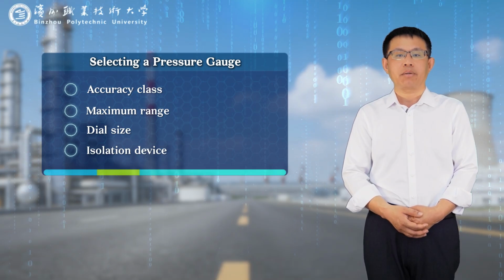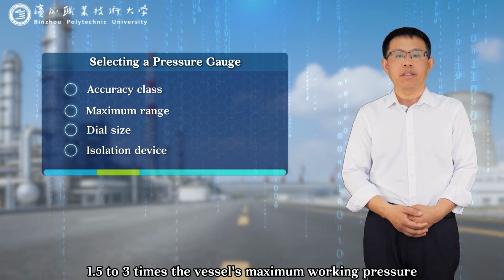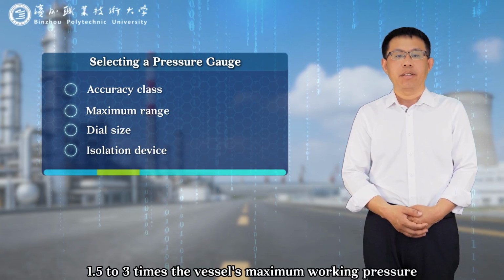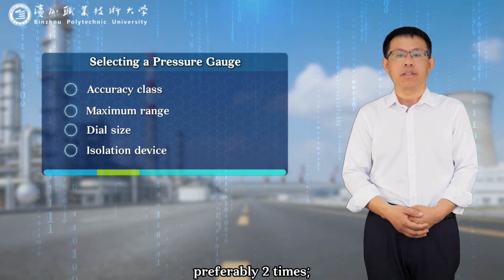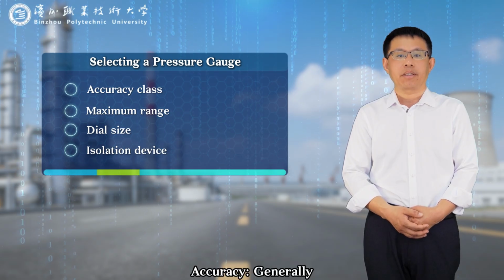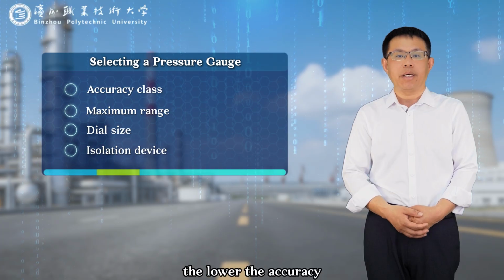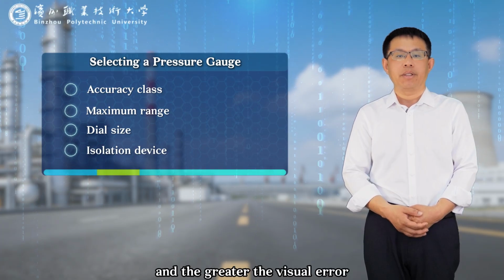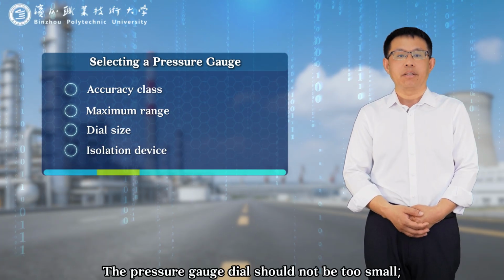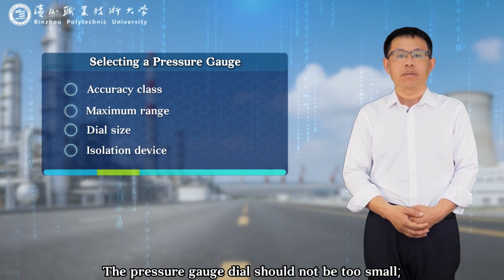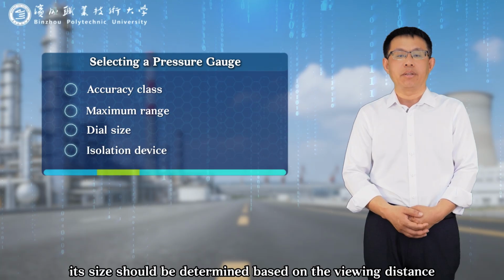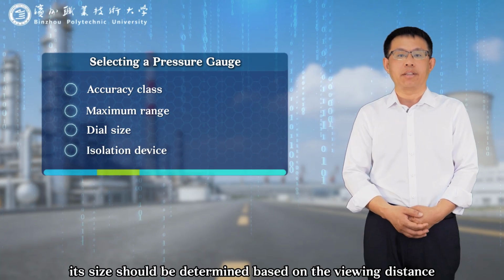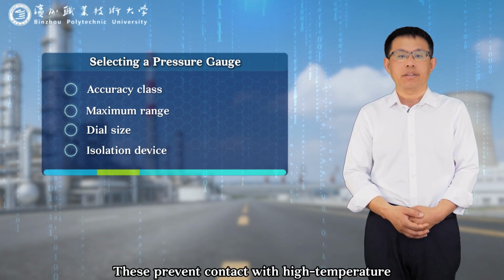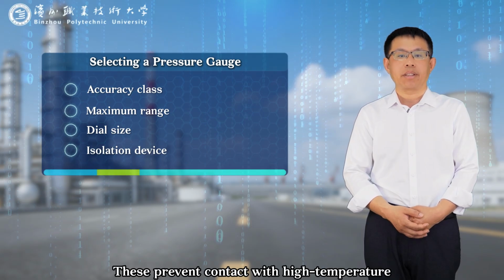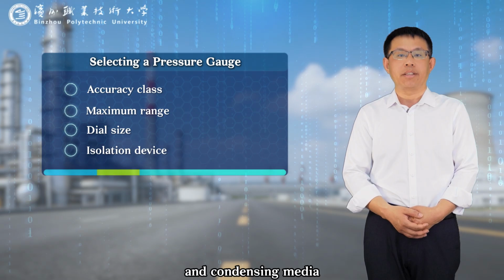Maximum range: 1.5 to 3 times the vessel's maximum working pressure, preferably 2 times. Accuracy: generally, the larger the range, the lower the accuracy, and the greater the visual error. Dial size: the pressure gauge dial should not be too small. Its size should be determined based on the viewing distance. Isolation devices: these prevent contact with high temperature, highly corrosive, and condensing media.